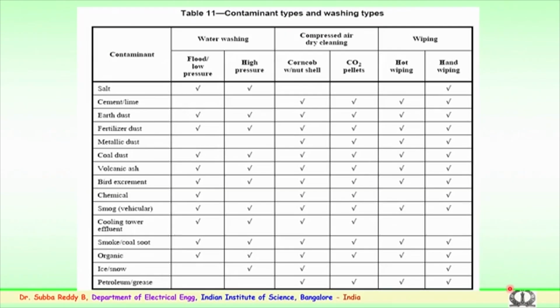So, various contaminants which we have described, the summary of this contaminants type and also the washing or cleaning types which are used. You can see various contaminants we have discussed. This is the water washing, various types, either low pressure or high pressure type of washing, compressed air dry cleaning using the corn cob or a walnut shell or carbon dioxide pellets, or sometimes wiping using the cloth. It could be hot wiping or a hand wiping. So, several methods are being used for cleaning the insulators both for dry and wet conditions.